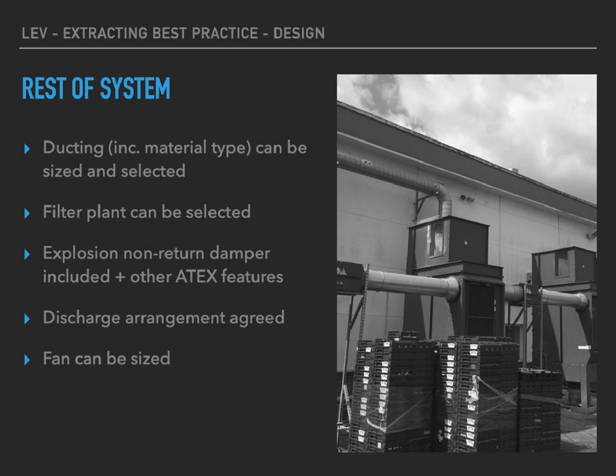You have other considerations to take into account, like ergonomics - the user's got to be able to use the system. We've got to take into account noise; these plants are noisy. The two you see in the photo, when they pulse clean, give a noise level of about 102 decibels. If you're running at night, you will get complaints from neighbors. We've also got to consider the structural loadings, not just the weight of the ducting, but the loading on stacks, wind loading on stacks, and things like that.